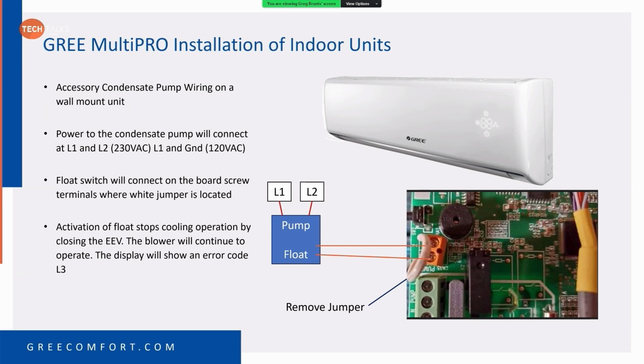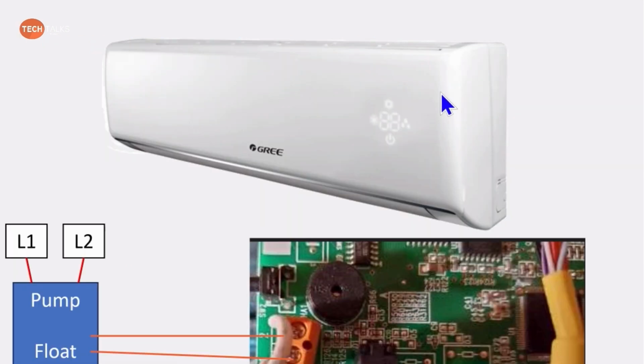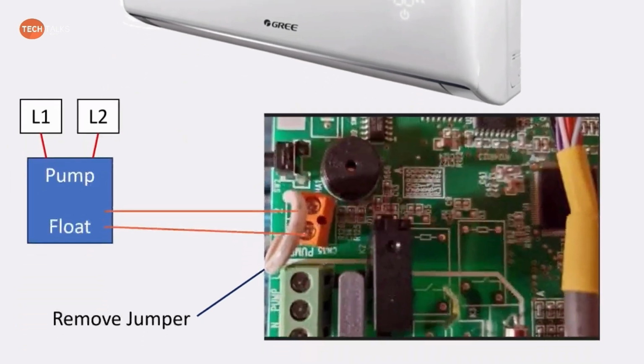To get to that little jumper on that wall mount, you do have to take the outer cover off, and you'll take the cover off the electric box assembly. But you don't have to pull that board all the way out. All you've got to do is slide that board towards you, and you only have to slide it a couple inches. That little jumper right there is right at the very end of the board. It's not that hard to get to, so just an FYI.